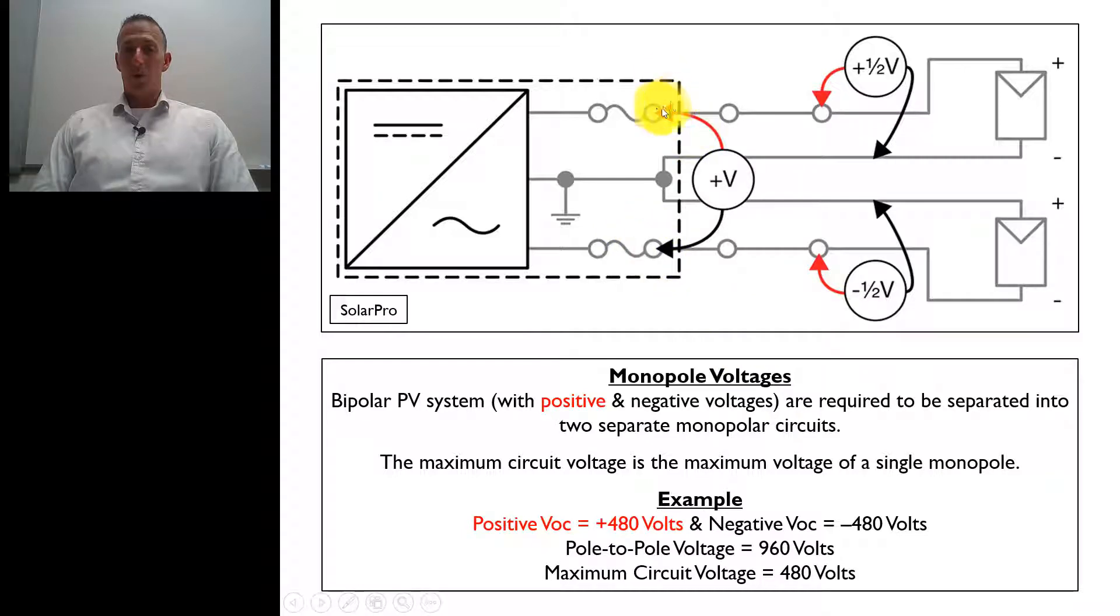We would have a negative 480 volts. If we measure pole to pole between the positive and negative, we would get 960 volts. So if we actually lost this center tap and we measured between here and here, we would actually have double what each of the monopole voltages are.